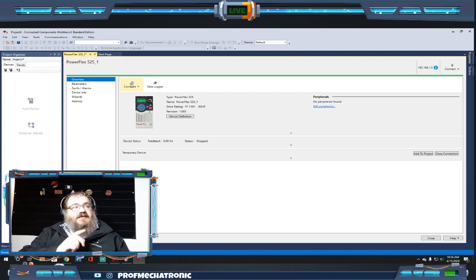But once you set that basic IP address structure with those 5 parameters on the manual screen on the VFD, Studio 5000 can do all the commissioning and setup you want. That's the advantage, and that's why a lot of automation technicians, control specialists, and maintenance skilled trades workers set it up manually on the VFD first, then use Studio 5000 for all configuration and commissioning. Once it's on the network, you can do everything much easier on the computer itself.